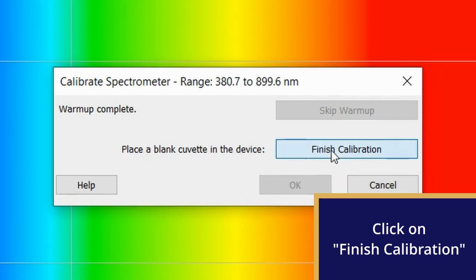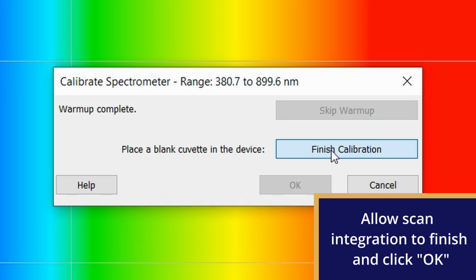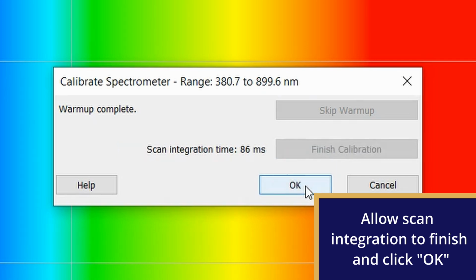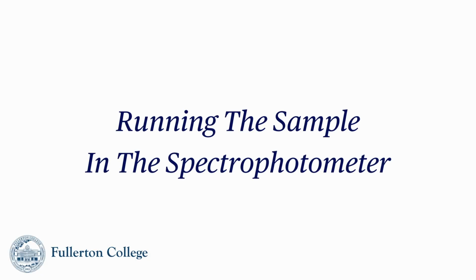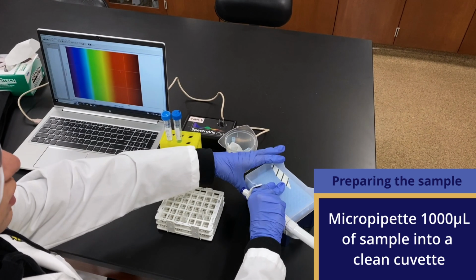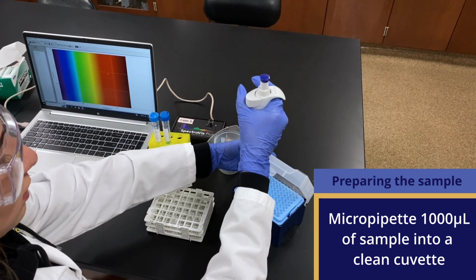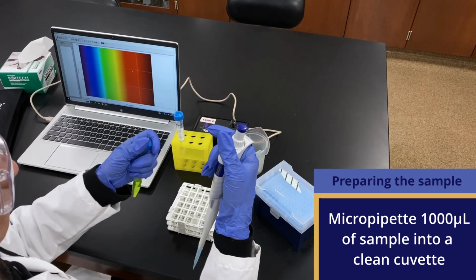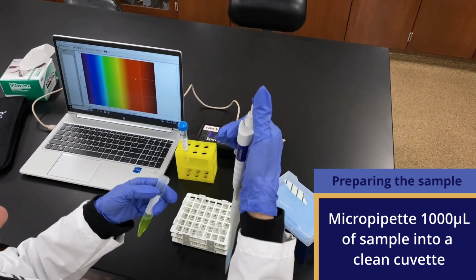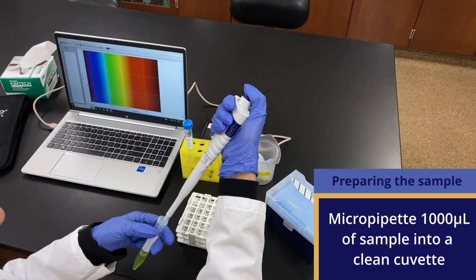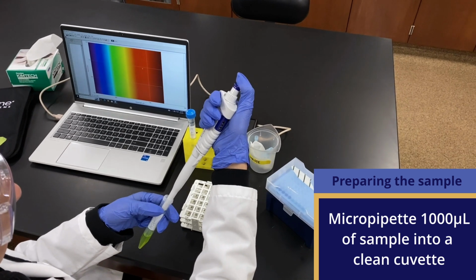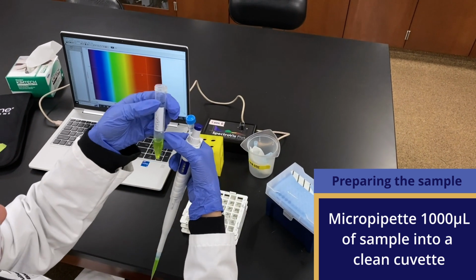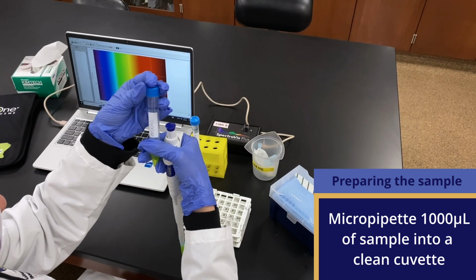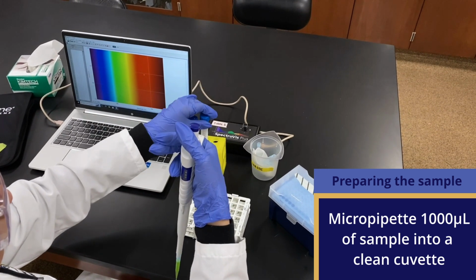Click Finish Calibration and wait for the process to complete. Once scan integration time is displayed, click OK to confirm. Now that the spectrophotometer is calibrated, we're ready to test our sample. Prepare a new clean cuvette and pipette 1000 microliters of sample into it, using the same pipetting technique as before. Since calibration only needs to be performed once, you can now proceed with testing multiple samples without repeating the calibration step.